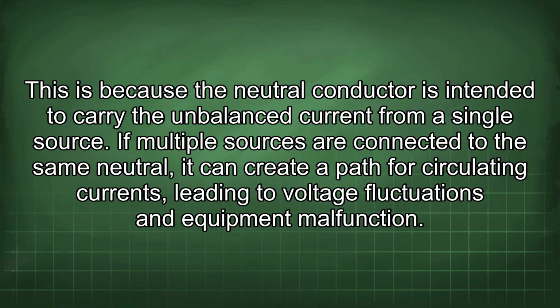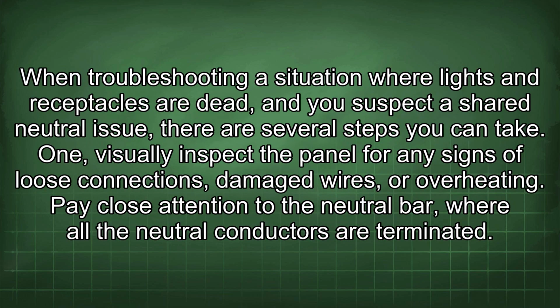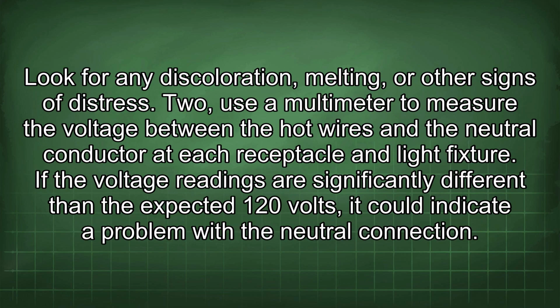fluctuations and equipment malfunction. When troubleshooting a situation where lights and receptacles are dead, and you suspect a shared neutral issue, there are several steps you can take. 1. Visually inspect the panel for any signs of loose connections, damaged wires, or overheating. Pay close attention to the neutral bar, where all the neutral conductors are terminated. Look for any discoloration, melting, or other signs of distress.